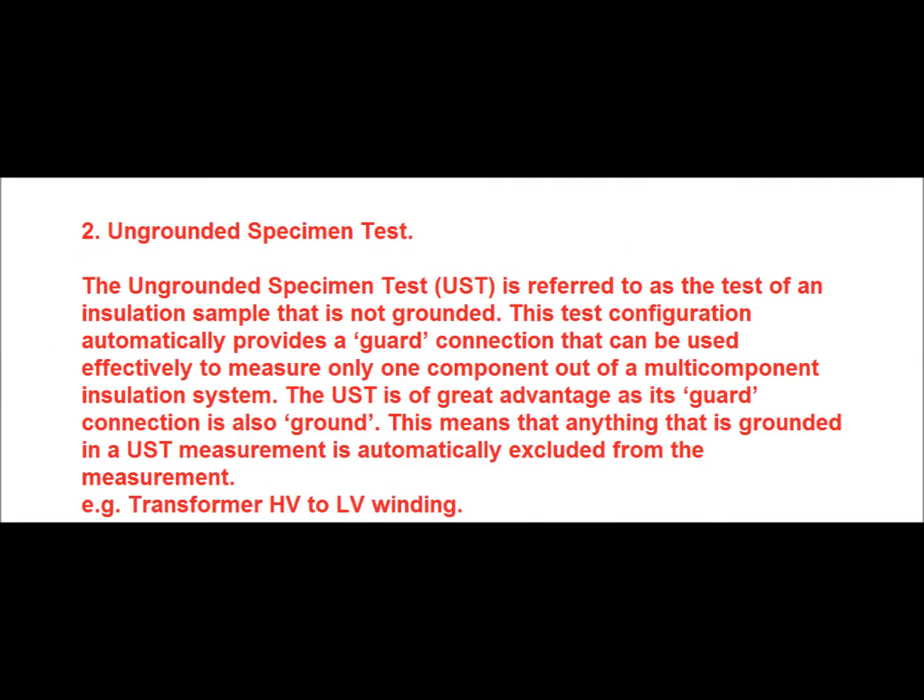The ungrounded specimen test, or UST, is referred to as the test of an insulation sample that is not grounded. This test configuration automatically provides a guard connection that can be used effectively to measure only one component out of a multi-component insulation system. The UST has a great advantage in that its guard connection is also grounded, meaning that anything grounded in a UST measurement is automatically excluded from the measurement.